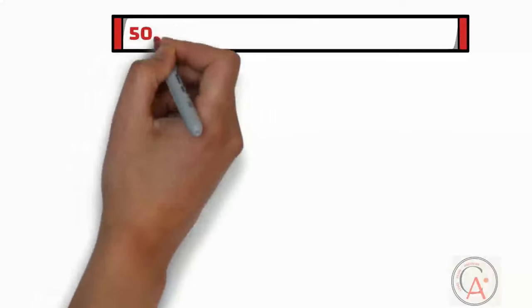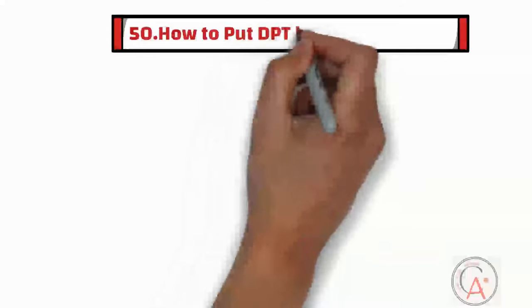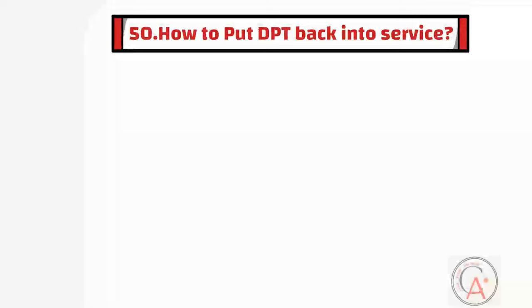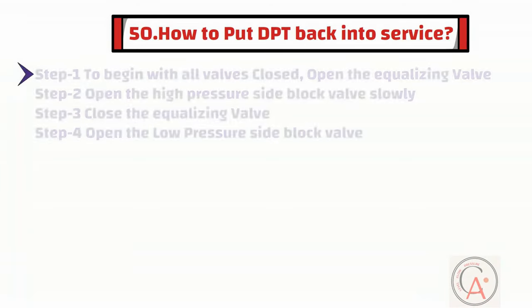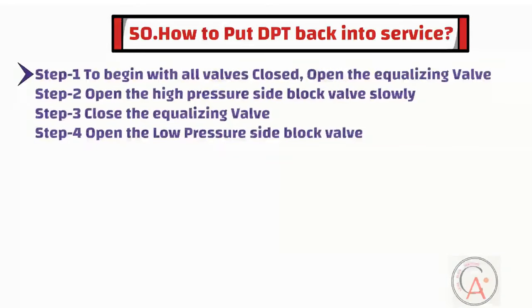Question fifty is: how to put DPT back into service? To put DPT back into service, begin with all valves closed, then open the equalizing valve. Then open the high-pressure side block valve slowly. Then close the equalizing valve. At the end, open the low-pressure side block valve.